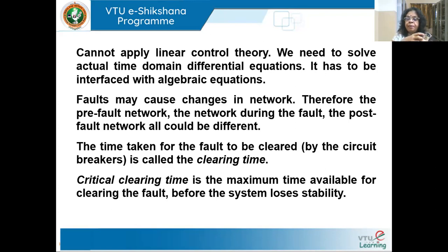Some people mistakenly say it's the minimum time. It's not the minimum time. It's the maximum time. That is the maximum time you have to clear the fault. You must clear the fault before that time, else the system will become unstable. Clear? So that is the critical clearing time.